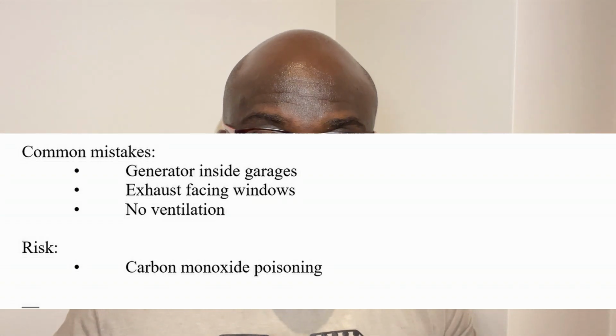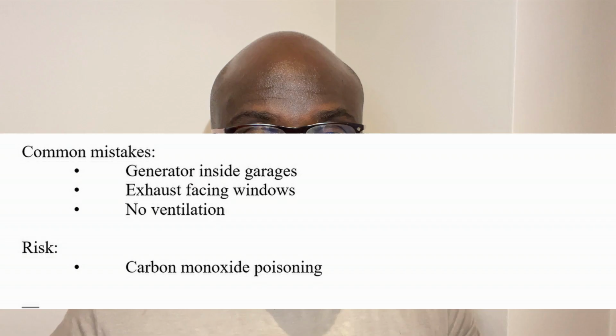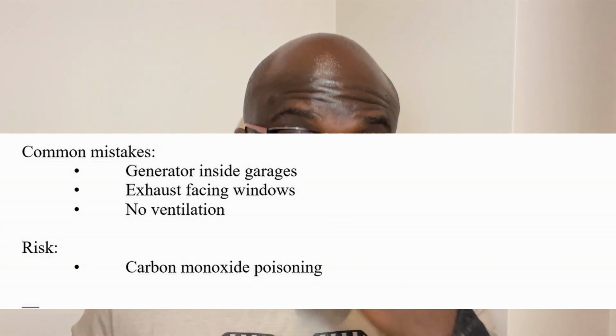And even as a home, you're supposed to have a carbon monoxide detector, not just for the generator, but also for your gas. As usual, another problem: no commissioning or load test. When you buy a generator, you're supposed to test it against your building. Put on all the air conditioning, or as many as possible based on the size of the generator. Put on the loads in the house. Fill it with fuel. Test it. Let's see if it can handle the load of the building.